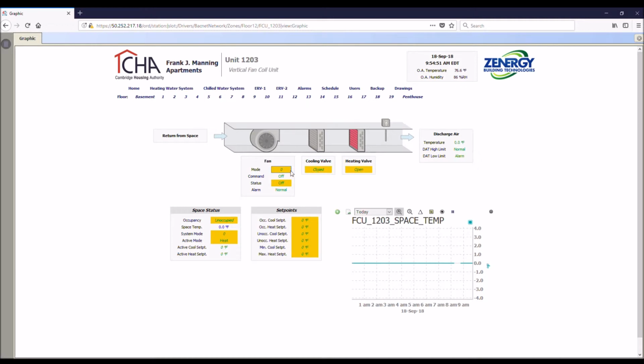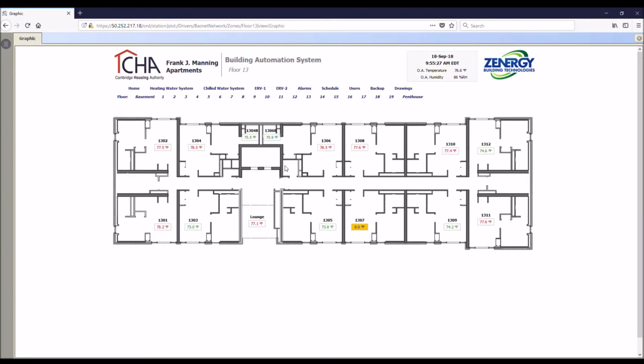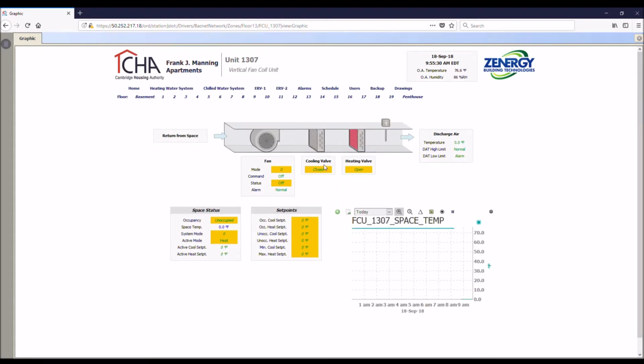The orange color, which is pretty much the same thing, just means that the point is at fault. That means that the system tried to do something, write to a point or read, and it ran into some sort of error, whether it timed out or it just wasn't able to write for some reason. It'll turn orange, and that is a fault. But effectively they're the same thing. It's some sort of communication issue. I'm not sure if we have any faults active system-wide, just because I had restarted the system earlier, and I think a lot of those faults cleared.